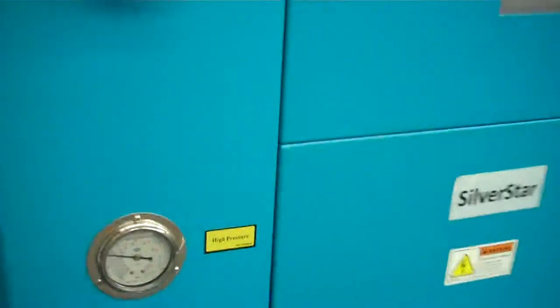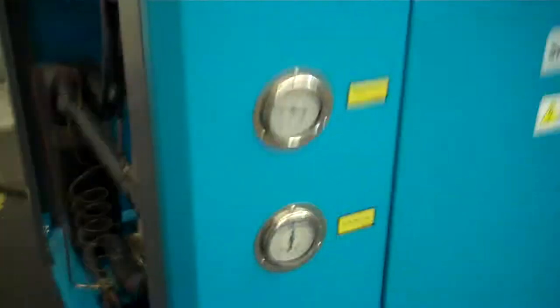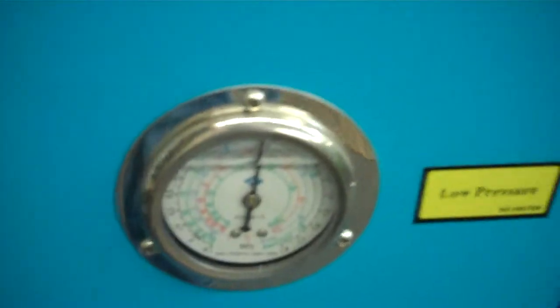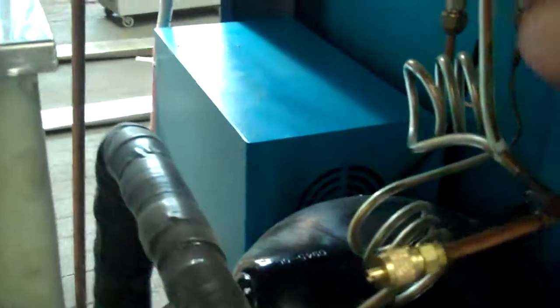We can go over a couple things while that time delay is going on. We have our high pressure and our low pressure refrigerant gauges for troubleshooting. The low pressure leads right back here to this connection, then it tees off and goes to our high-low pressure switch there. Similarly, the high pressure comes here, and that also tees off and goes to the high and low pressure switch that's right there.